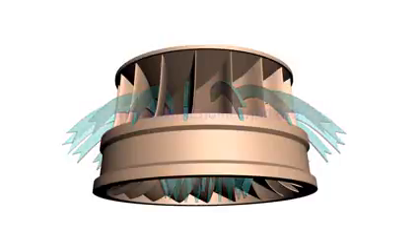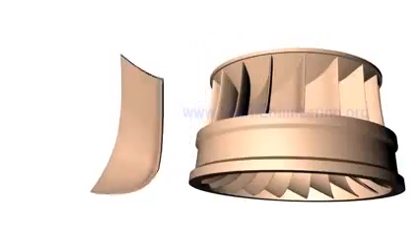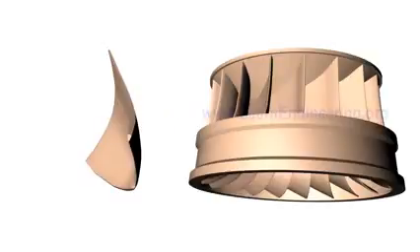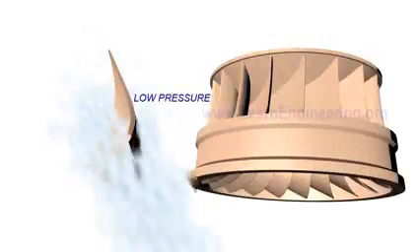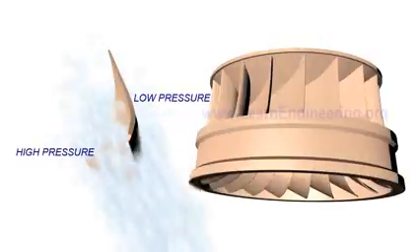Francis Turbine blades are specially shaped. You can note that blades have thin airfoil cross sections. So when water flows over them, a low pressure will be produced on one side and high pressure on the other side. This will result in a lift force.